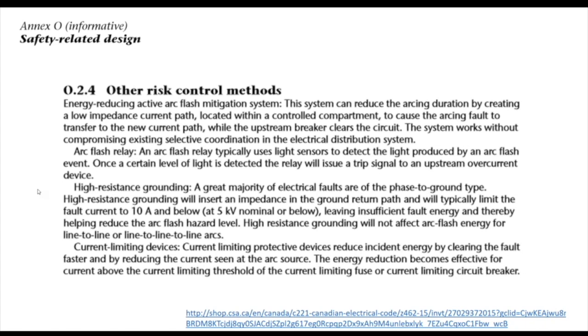High resistance grounding. It was something we used in our power plants. It was put in place by our electrical engineers in the design phase, and it was very, very effective. It was much better for safety, and there was huge accountability in our power plants here in Ontario to ensure that we could keep the grid up and running. So it's about worker safety, it's about reliability, it's about applying the electricity you need, whether it's to the public and to businesses, or just in your own place to make sure that you can continue to run production. And current limiting devices. All these things, if you ask a good engineer what you can do, they can come up with some really good ideas that are effective and give you a good return.